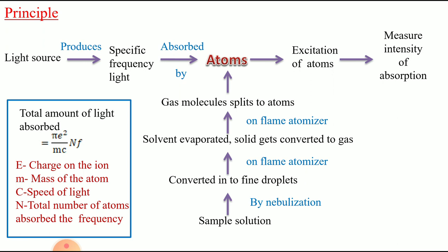The principle of atomic absorption spectroscopy is similar to flame photometry. The sample solution is converted into fine droplets by nebulization. These fine droplets are then exposed to the flame atomizer, where the solvent is evaporated. The solute solid particles are converted into vapor or gaseous state, and then the molecules are converted to atoms by receiving thermal energy from the flame.